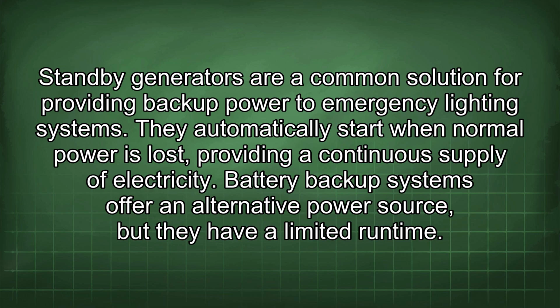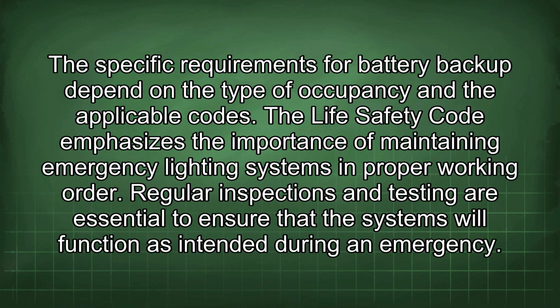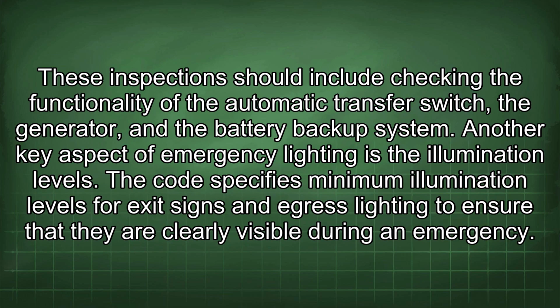Battery backup systems offer an alternative power source, but they have a limited runtime. The specific requirements for battery backup depend on the type of occupancy and the applicable codes. The Life Safety Code emphasizes the importance of maintaining emergency lighting systems in proper working order. Regular inspections and testing are essential to ensure that the systems will function as intended during an emergency. These inspections should include checking the functionality of the automatic transfer switch, the generator, and the battery backup system.